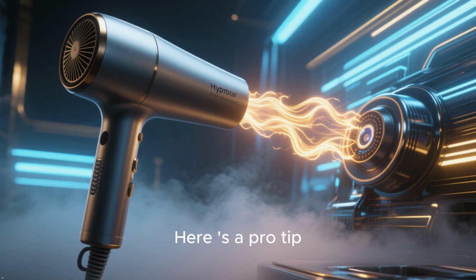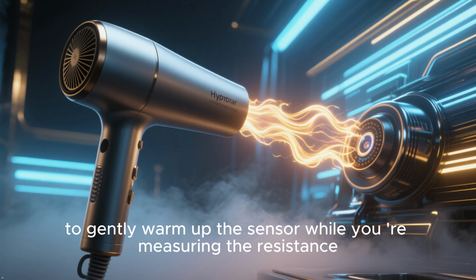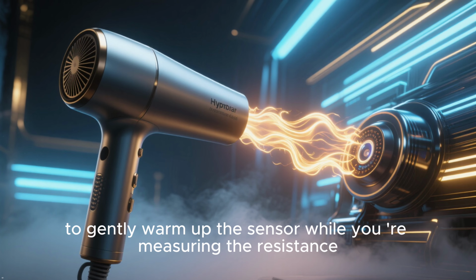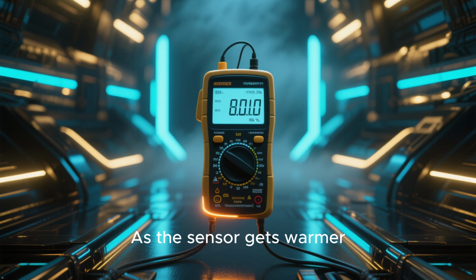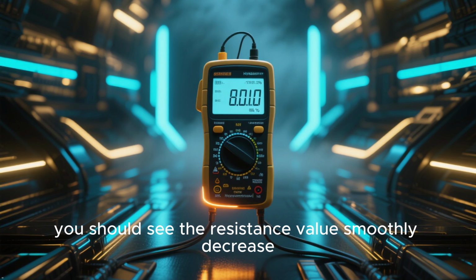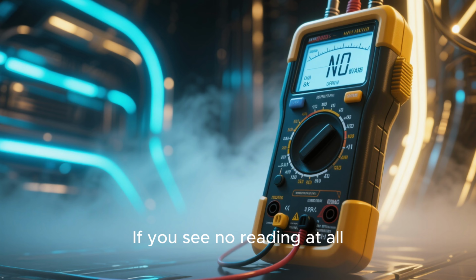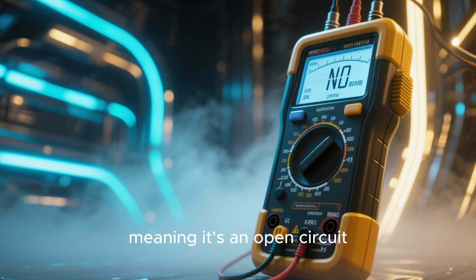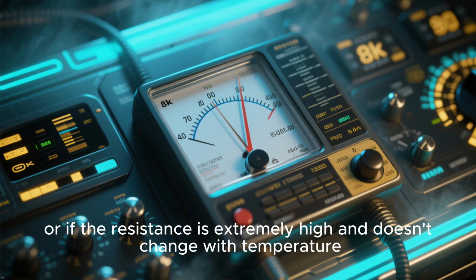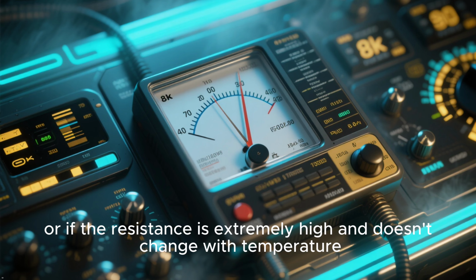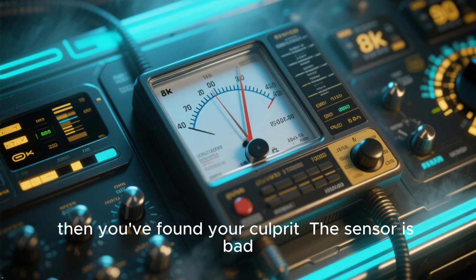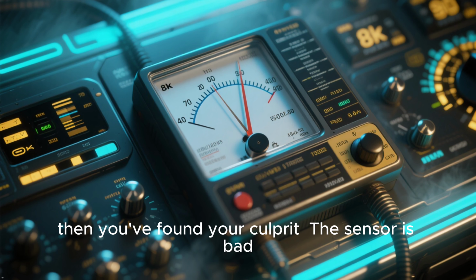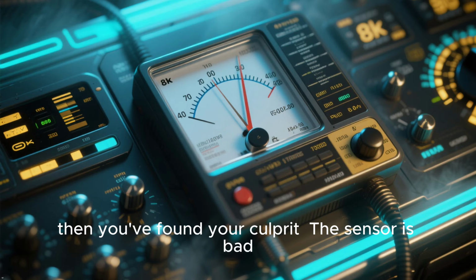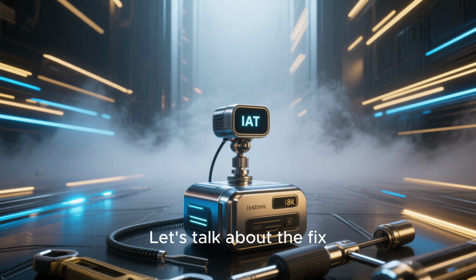Here is a pro tip. You can use a hairdryer to gently warm up the sensor while you're remeasuring the resistance. As the sensor gets warmer, you should see the resistance value smoothly decrease. If you see no reading at all, meaning it's an open circuit, or if the resistance is extremely high and doesn't change with temperature, then you've found your culprit. The sensor's bad. Let's talk about how to fix it.